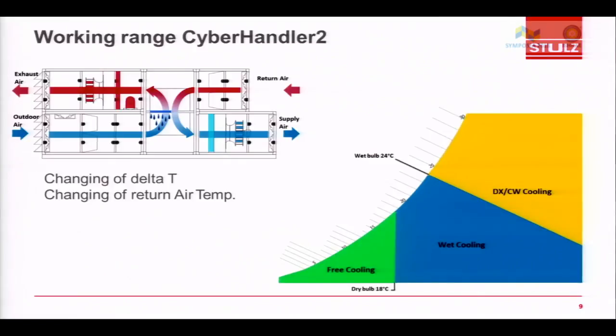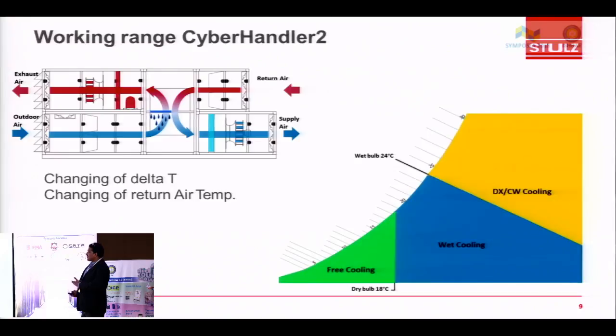They have divided cooling into 3 modes. One is free cooling, one is wet cooling, and one is DX and chilled water cooling, depending on the customer's choice whether he wants to go with DX or chilled water. There is a change of delta T, changing of internal temperature. So anything below wet bulb 24 degrees Celsius, wet cooling is going to take place in the data center.